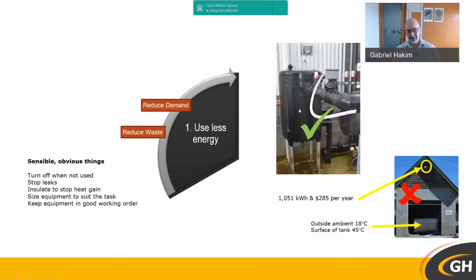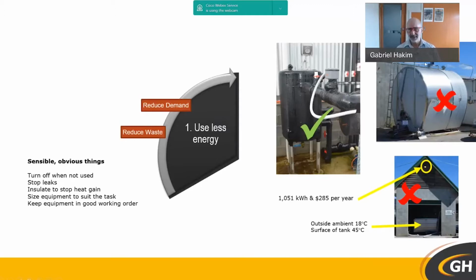Having cooling systems that are well insulated is another way of stopping heat gain and therefore reducing extra cooling load. This tank was outside, and you can imagine what happens during summer. The ambient temperature outside was 18 degrees, but the surface temperature of the tank measured 45 degrees, and you could feel the heat coming through into the inside of the tank. You can imagine the impact that has on cooling.